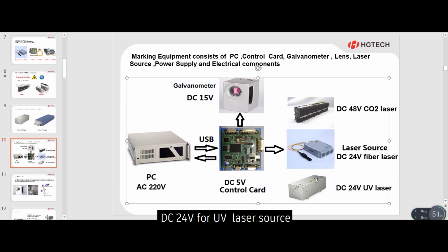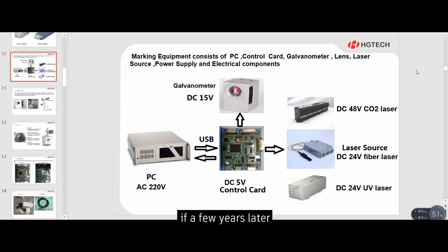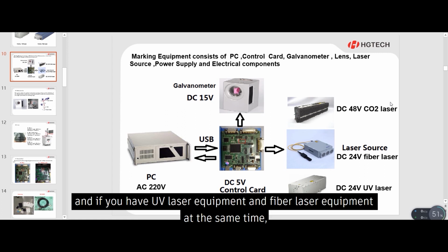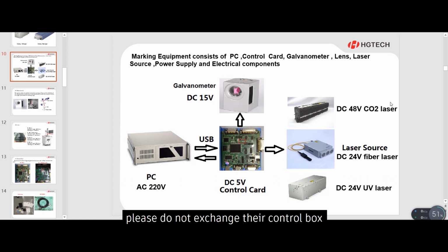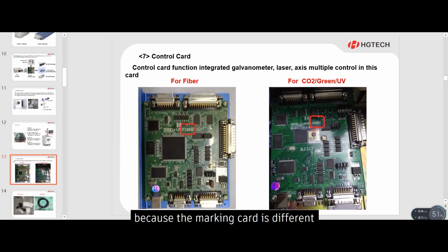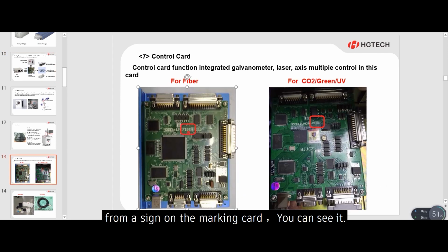for the UV laser. If a few years later there is some issue, please follow this picture and test the voltage with a multimeter. And if you have UV laser equipment and fiber laser equipment at the same time, please do not exchange their control box, because the marking card is different. From a sign on the marking card, you can see it.